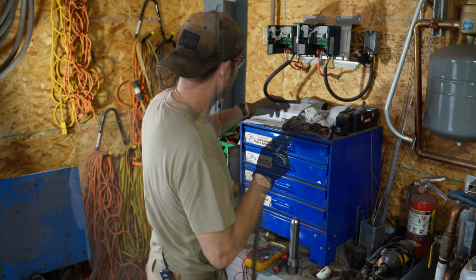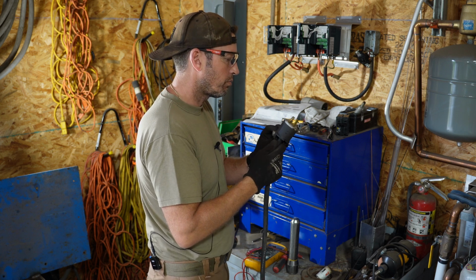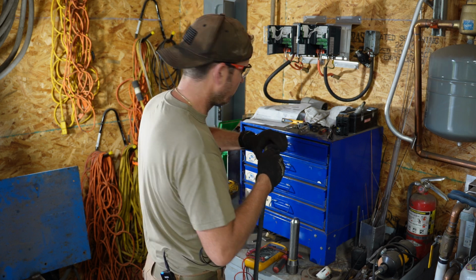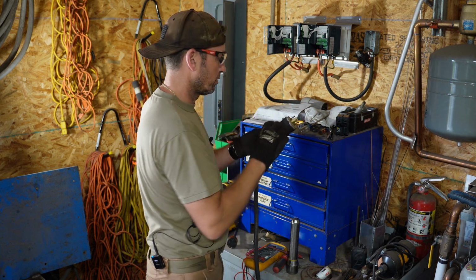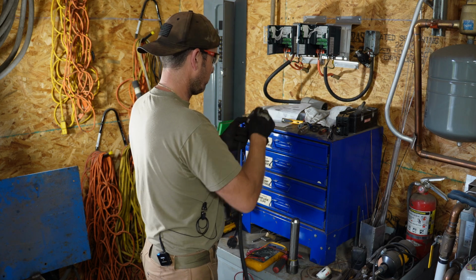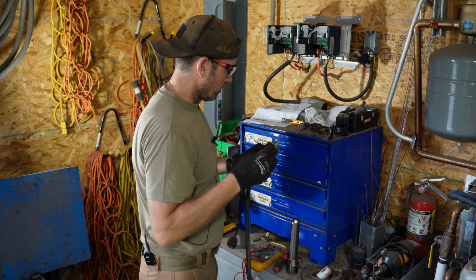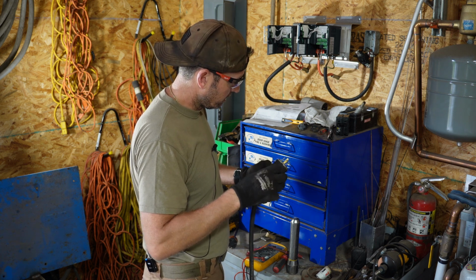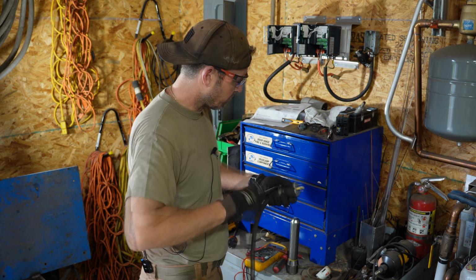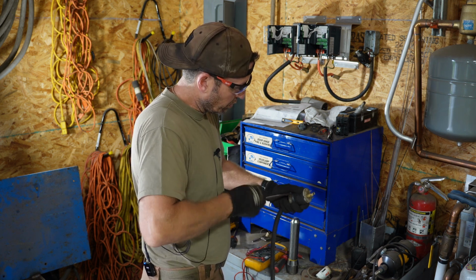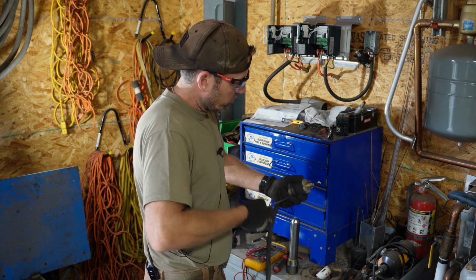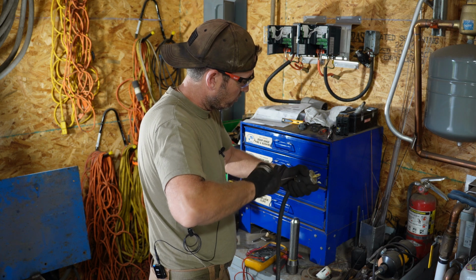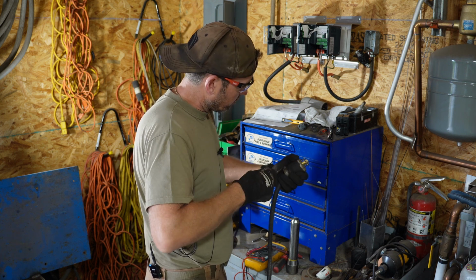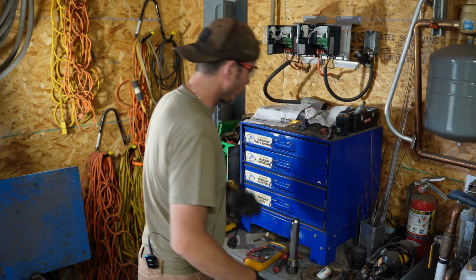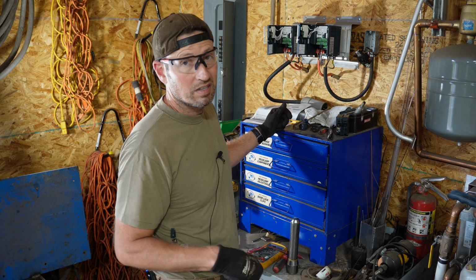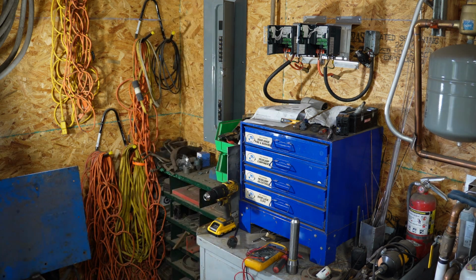Everything checks out there. Something else I learned - I definitely did not put the right power factor, or cosine, in there, so that's something I'll be changing shortly. I should have known better, because pretty much no motor, especially one this old, is 100% efficient. The cosine power factor isn't written on the nameplate, but I was able to find a data sheet, though it's for a newer model of the same model number. So I'm going to assume the older model is even worse than the newer one. On top of that, according to the date code, the motor we're working with is a 1974 model. But it all tests out good, so it should work.